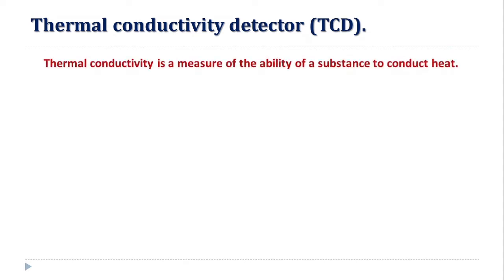Thermal conductivity is a measure of the ability of a substance to conduct heat. This is the principle used in the thermal conductivity detector. The ability of the substance to conduct heat depends upon what the substance is, what is the composition of that component. That's why this technique is used for the identification and measurement of the concentration of those components.